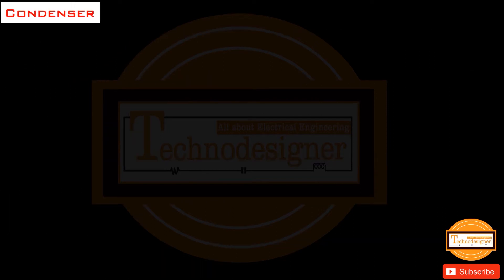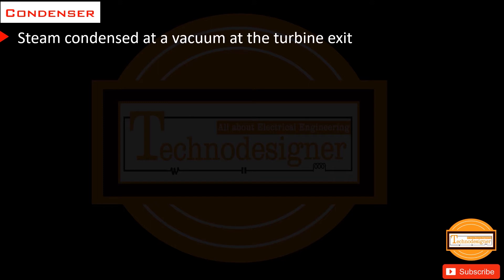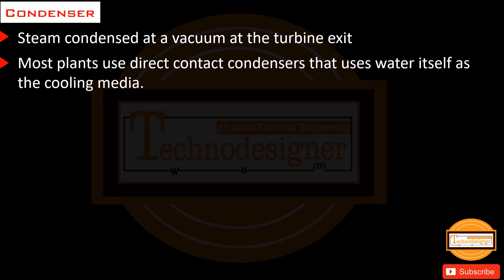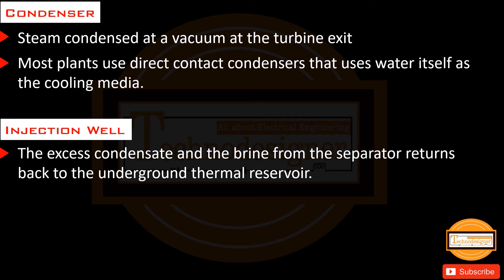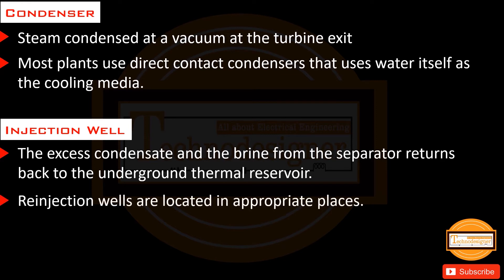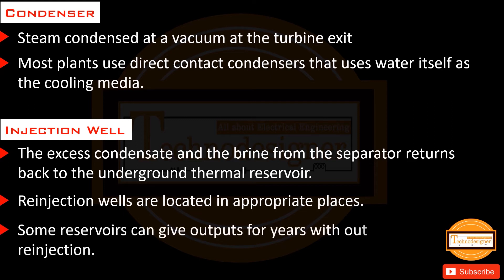Steam is condensed by a vacuum at the turbine exit. Most plants use direct contact condensers that use water itself as the cooling medium. The excess condensate and brine from the separator return to the underground thermal reservoir via re-injection wells located in appropriate places. Some reservoirs can provide outputs for years without re-injection.